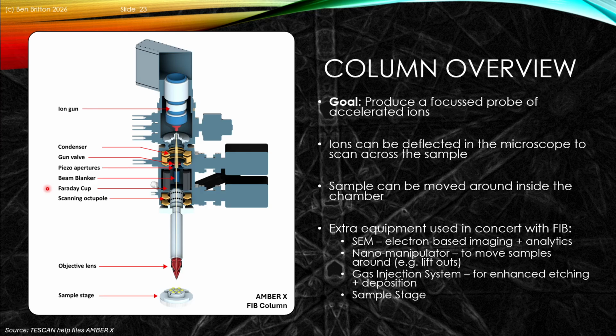Now there are a few other bits and pieces that are useful. We have the Faraday cup that enables us to measure the probe current of the beam, and that can be especially useful when we want to understand, for instance, the ion dose that our sample receives. So the goal of our focused ion beam system is to create a focused probe of accelerated ions. The ions themselves are typically accelerated, often anywhere between 200 electron volts and say 30 kilo electron volts. The ions themselves are often positively charged, and they can be deflected in the microscope to scan across the surface of our sample and interact with the surface of our sample for our range of applications.